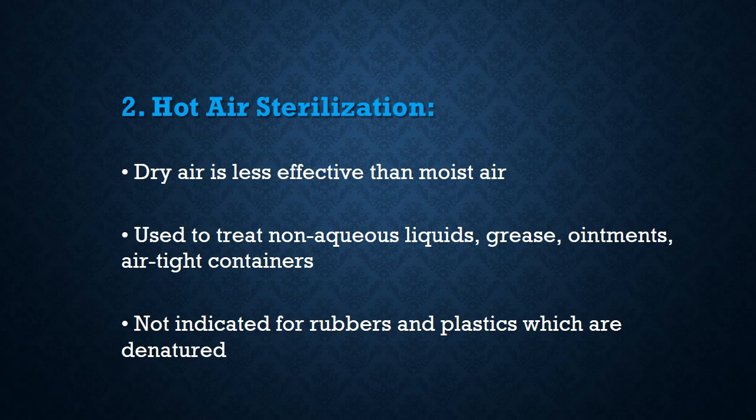In addition, it is used for non-aqueous liquids, grease, ointments, and airtight containers, especially if the containers are not made of plastic. Lesser temperatures for prolonged time can be used in case of plastics and rubbers, but generally, if other better methods are available, hot air sterilization is restricted to ceramics and metal objects.